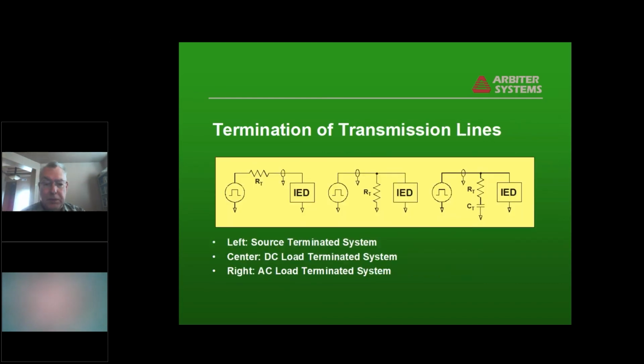Here are some simple schematics showing, on the left, a source terminated system. This is where the clock itself includes a series resistor equal to the characteristic impedance of the coaxial line, 50 ohms typically. The second one has a load applied at the far end of the transmission line across the IED input, again equal to the characteristic impedance, 50 ohms typically. And then on the far right is called AC termination, which has the resistor, also equal to the characteristic impedance, in series with a capacitor. We do that to reduce steady state power loss.